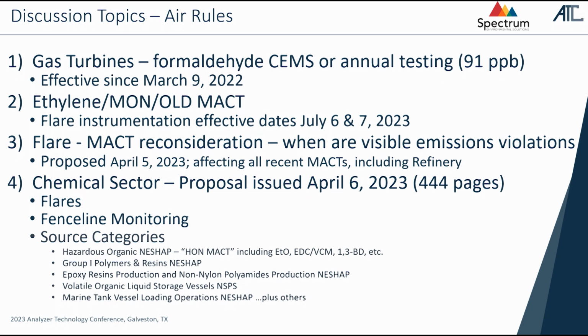The word downtime is not in the rule. So the analyzers are supposed to run on these flares continuously. But for the smoke issue, you got about 3 excursions allowed. You could have a smoking flare event, and it could happen 3 times. The only thing they did is say that if it were a major force majeure, a power outage, something outside of your control, that didn't count towards those 3 smoking flare events in a 3-year period.